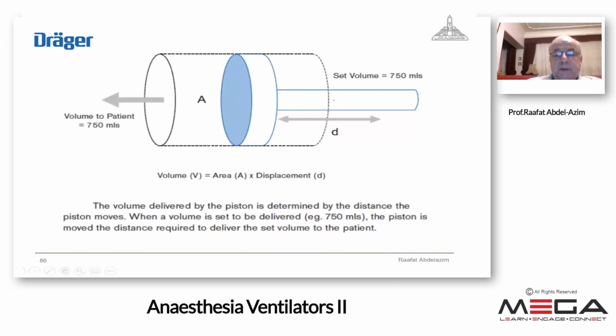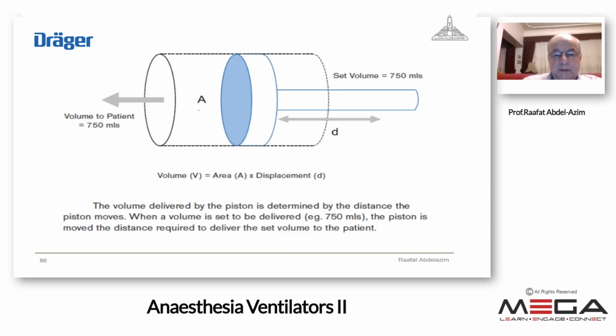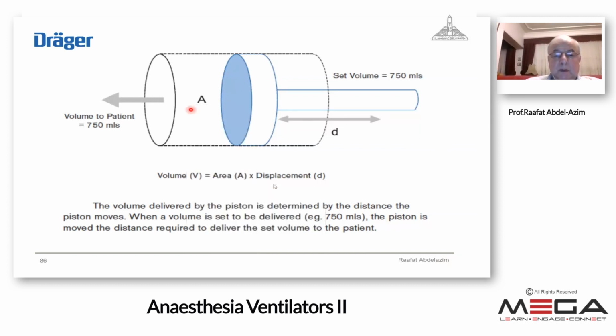This is the piston, the diagram showing the piston. Moving the piston to the left means that the contents of the piston, that's the patient gas, will go to the patient into the inspiratory limb. This depends on the distance I move it according to the preset tidal volume. This movement is only mechanical. It doesn't depend on the driving gas, as I said before, for the ascending bellows ventilator.